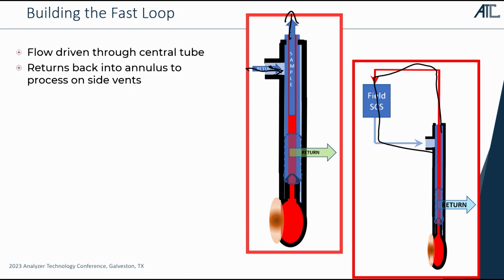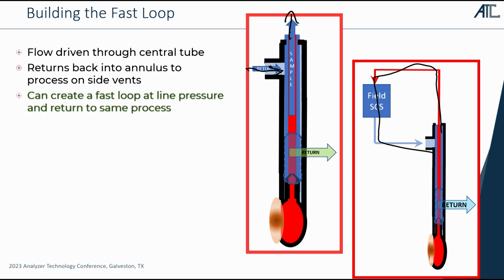Run some tubing around it. You preferentially use fairly large bores so they don't have much pressure drop. So this creates a fast loop that allows us to extract from the process pipe and return back into the process pipe at the same pressure. There's effectively no difference in pressure. There's a few kPa, but it's enough to continuously drive a loop through there.